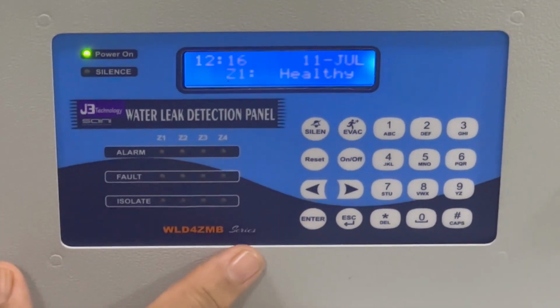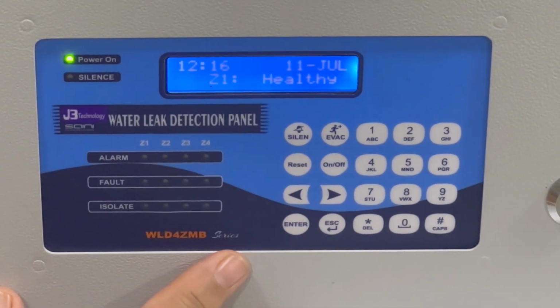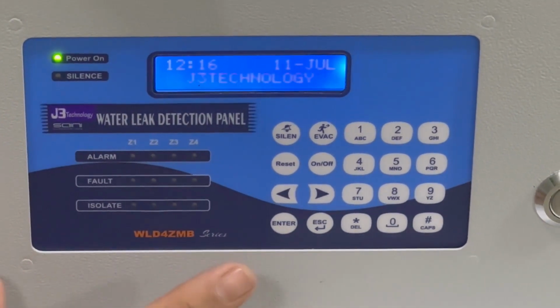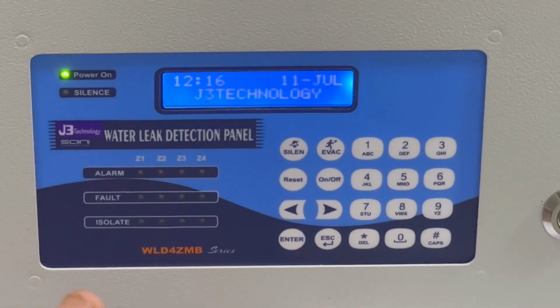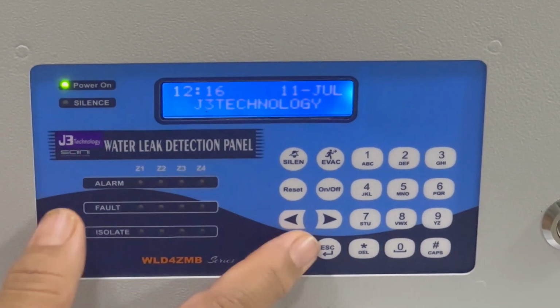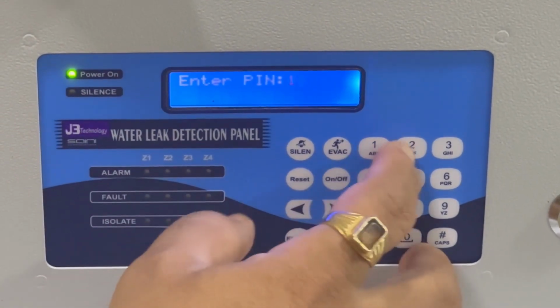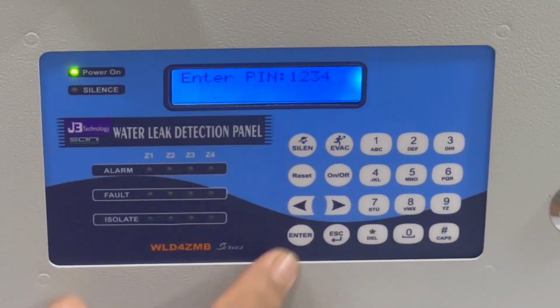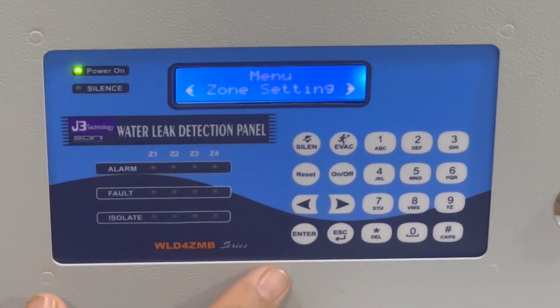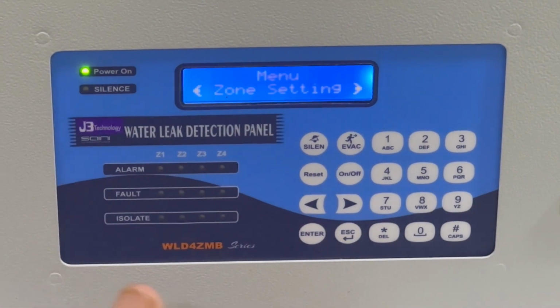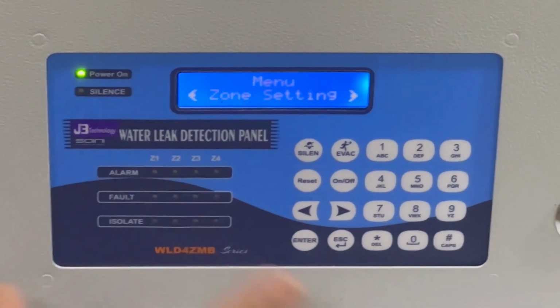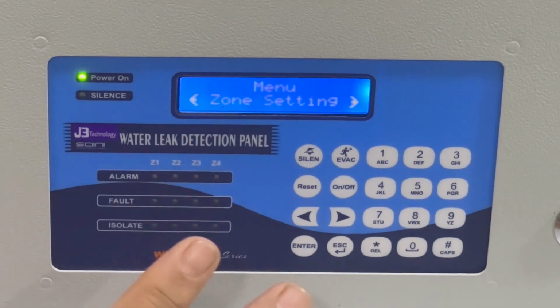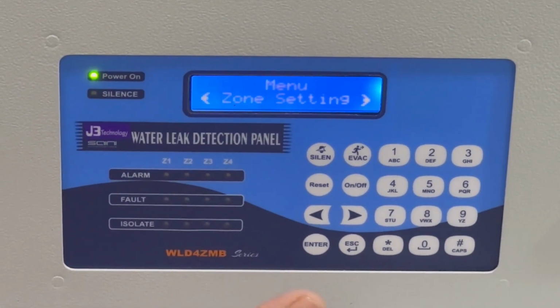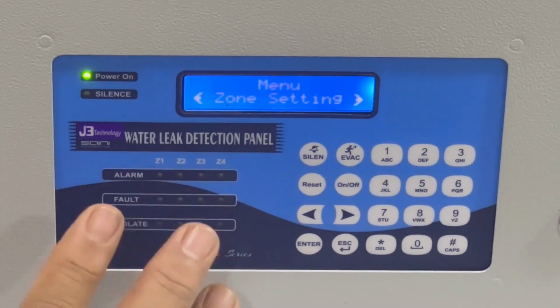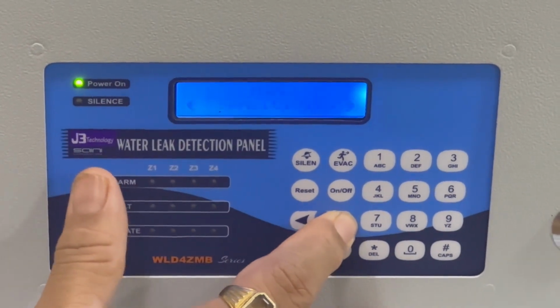Now guys, I will show you the last option, that is the factory reset. As everybody is aware, the factory reset is a very last option. Suppose you want to reconfigure the panel, or the site has changed, or the panel is not responding properly. At that time you can use this factory default setting option, which you can see on the menu.